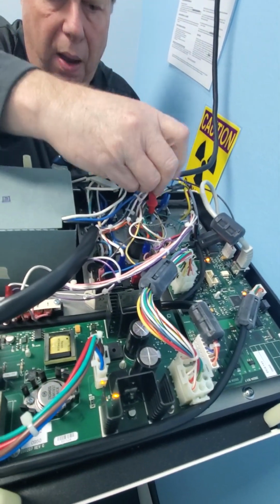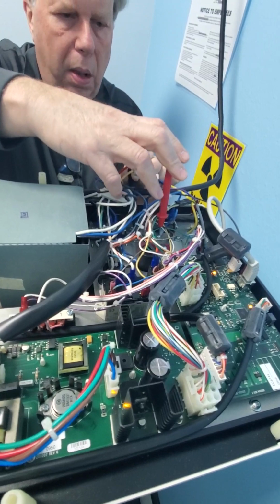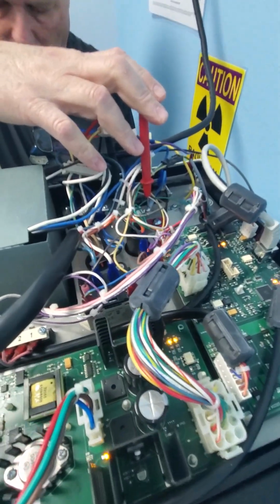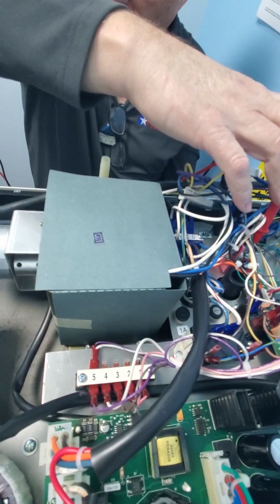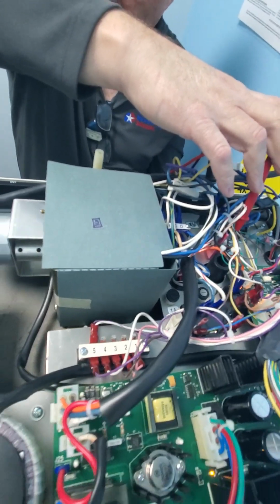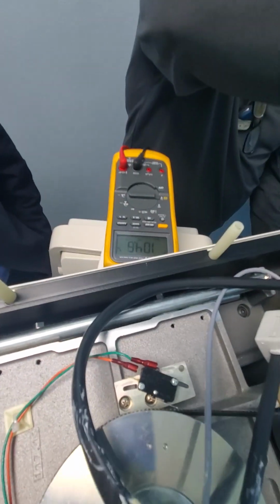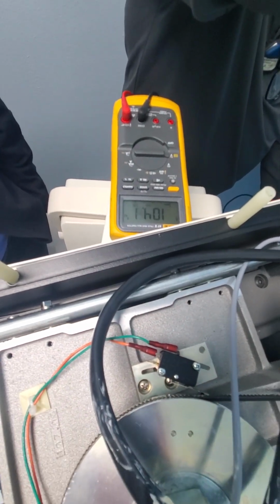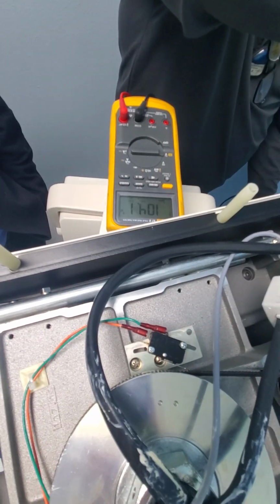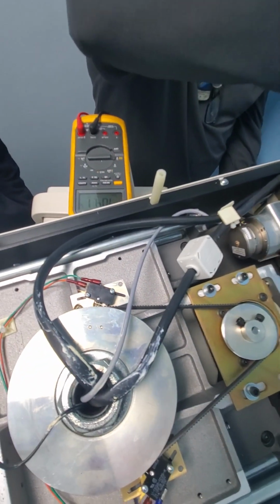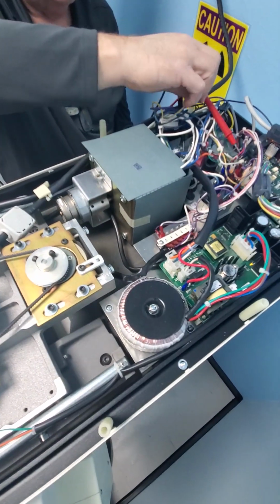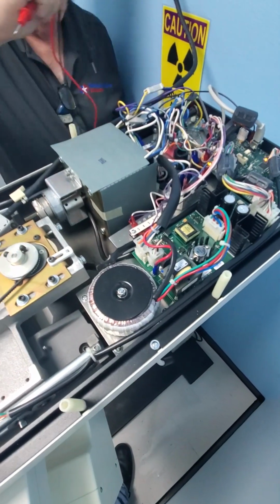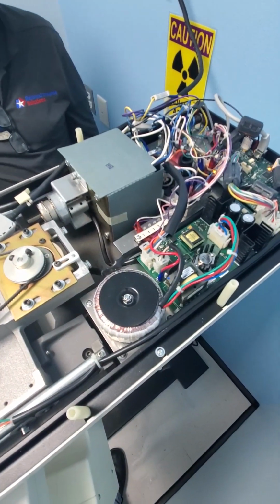107, that's a little high. That's 104. If they get KV errors again and poor image quality, I would probably look into getting this board, the power supply. And then run through the calibration again when you put the board in there.